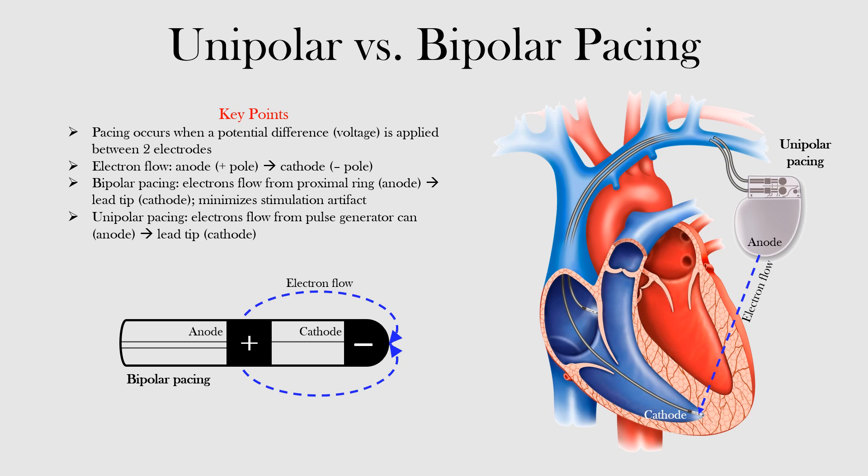With bipolar pacing, the potential difference occurs between the proximal ring, which is the anode, and the lead tip, the cathode. In contrast, with unipolar pacing, the potential difference occurs between the lead tip and the pulse generator, such that electrons flow between the pulse generator and the lead tip.